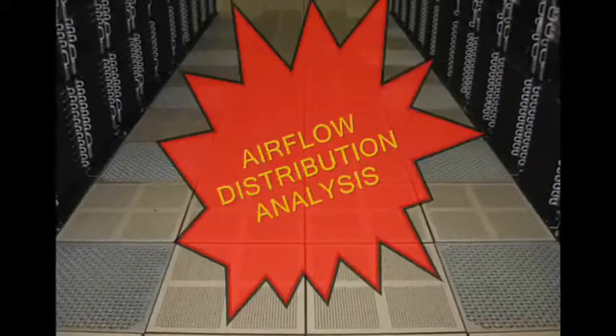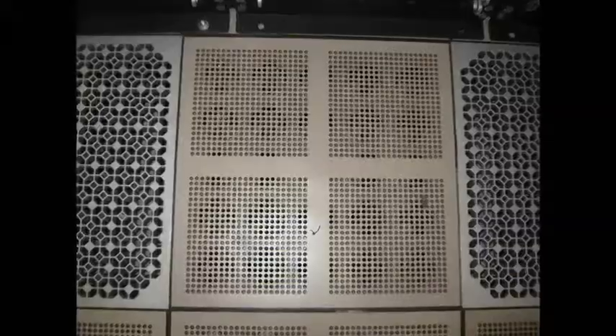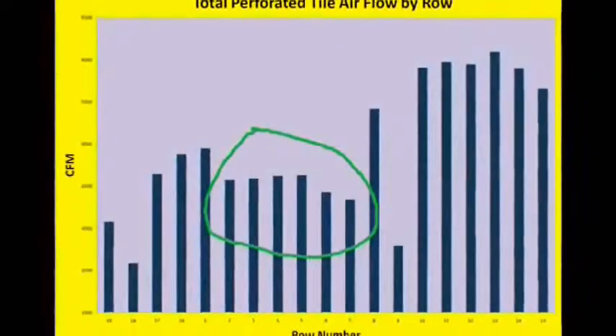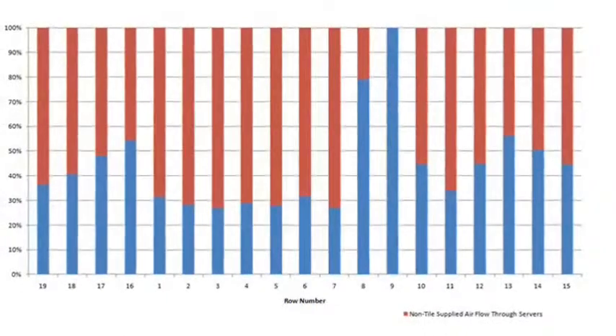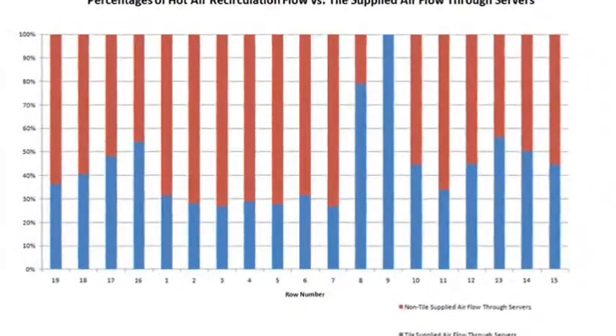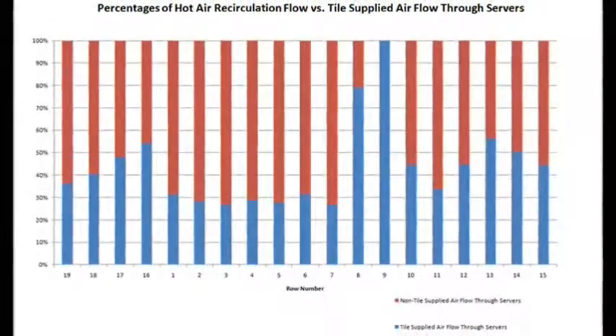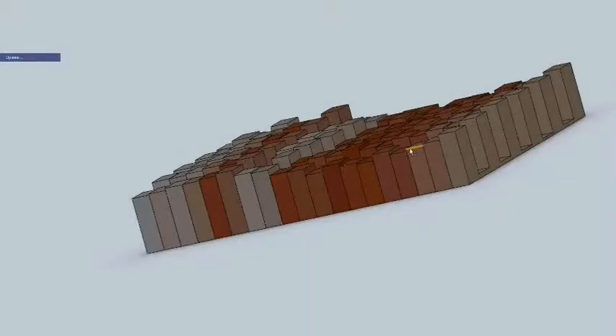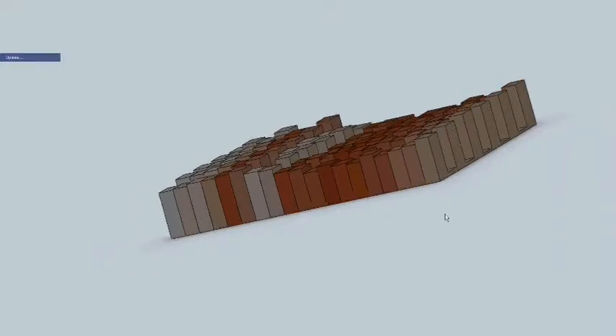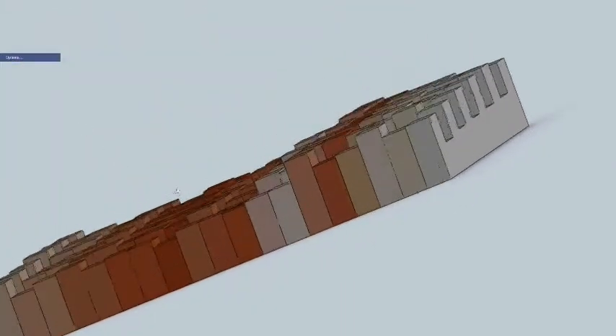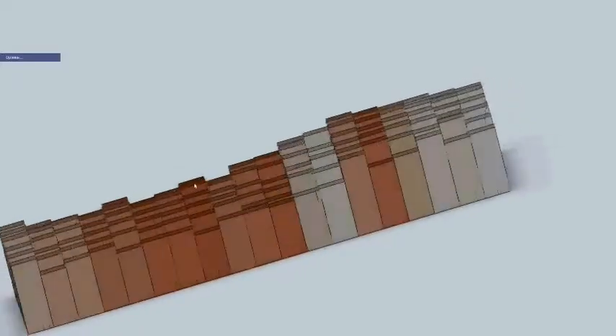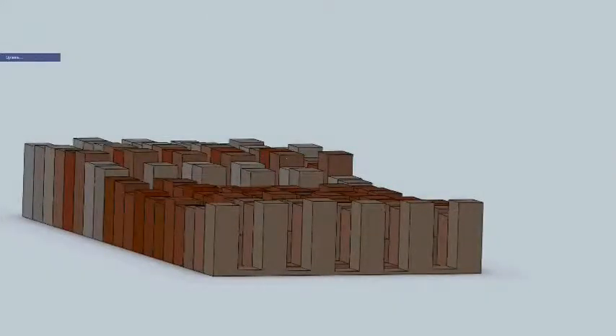To fully understand the airflow distribution in your facility, we take volumetric airflow rate readings at every perforated tile. We typically see that areas with high amounts of hot air recirculation are largely undersupplied by the perforated tile airflow. Another metric we provide will tell you what percentage of air under-provisioning or over-provisioning is occurring at each rack. This metric is a great indicator of the effectiveness of your CRAC unit layout. Here is a three-dimensional plot of airflow through all perforated tiles in a data center experiencing under-provisioning. Rows in the middle of the room had high amounts of hot air recirculation at rack inlets because of the low perforated tile flow rates. This data center had too few CRAC units cooling these areas.